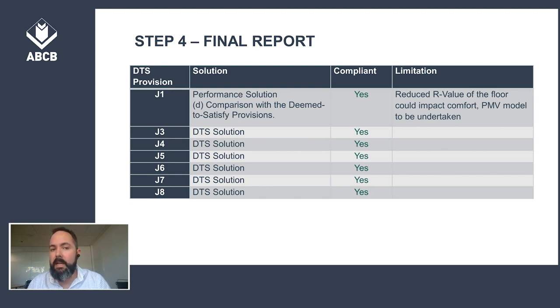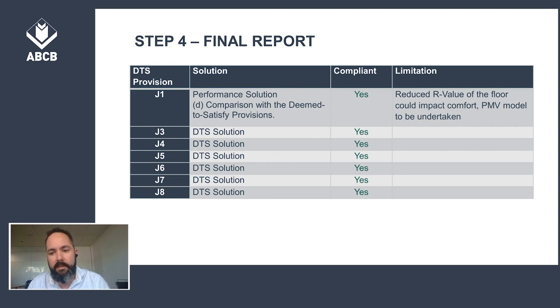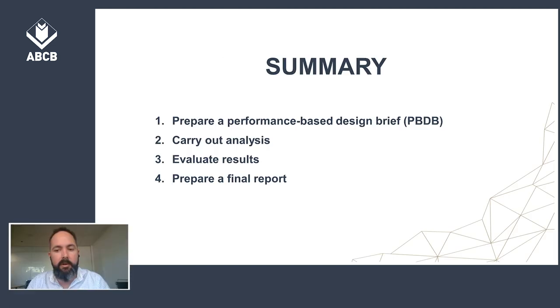Thermal comfort may have been impacted, and the group agreed on undertaking a thermal comfort analysis to ensure thermal comfort is achieved. A predicted mean vote of negative one to plus one is to be achieved across not less than 95% of all occupied zones for not less than 98% of the annual hours of operation of the building.